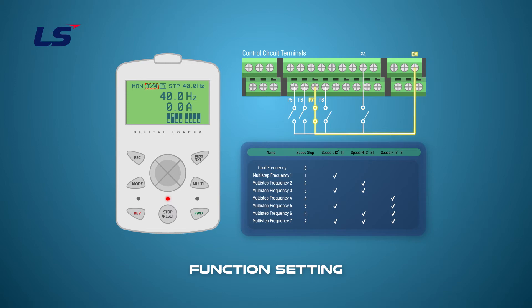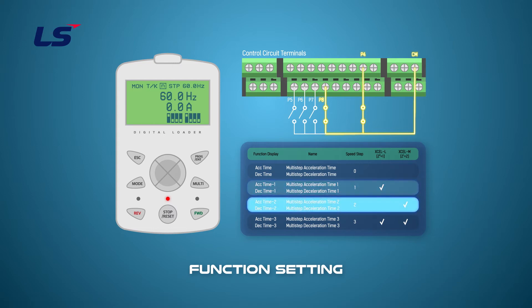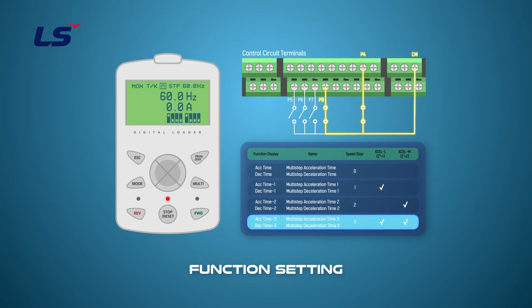Multi-step acceleration-deceleration also operates in the same sequence. Therefore, steps 1, 2, and 3 work by the input combinations of XCEL-L and XCEL-M. The input status of the multi-step acceleration-deceleration is not displayed on the keypad, but you can check the input status through the DI status parameter.